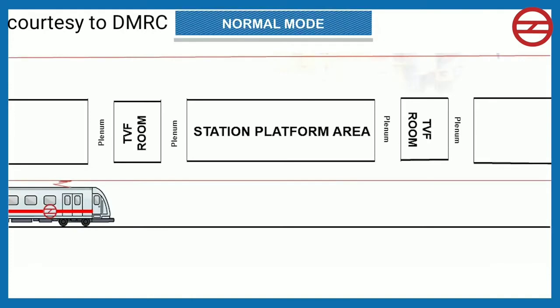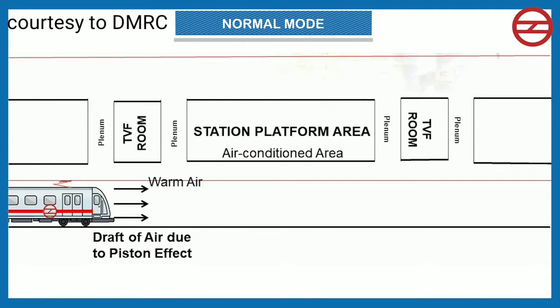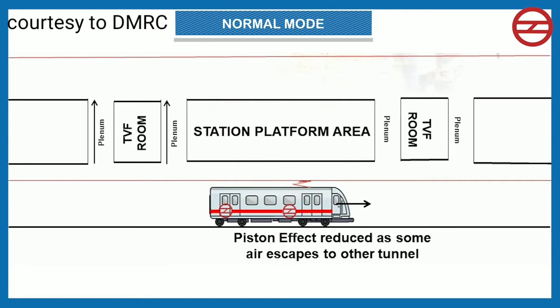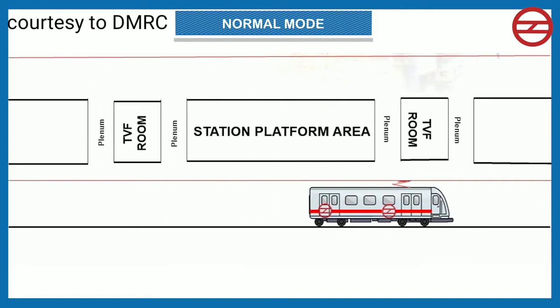First, normal mode. Normal mode means everything is normal in station and tunnel area. The TVS equipments are in off state but ready for any operation. However, when a train comes, it brings a draft of air due to piston effect. Therefore, in tunnel ventilation system, a method is devised to reduce the effect of this draft of air. Plenums connecting both the tunnels are provided in the system, as can be seen here. When train brings draft of high pressure air, some air escapes to the other tunnel, thereby reducing the piston effect.